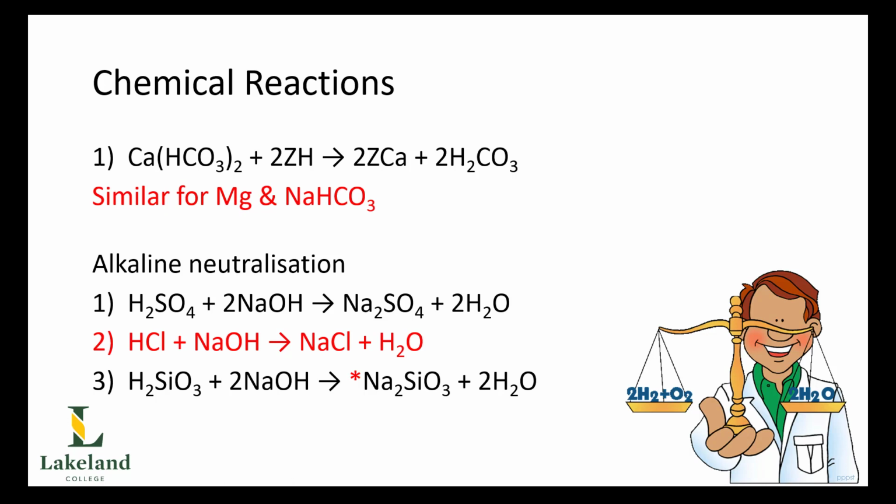Now, silicic acid, when it combines with our sodium hydroxide, causes a problem in that it forms sodium silicate. And the reason why we don't want sodium silicate is because this will produce an extremely hard and tenacious scale in the boiler. And it can also carry over and cause silica scaling downstream in end-of-steam users, like steam turbines, for example, when the pressure drops below 4150 kPa. So because we're producing sodium silicate on the effluent of this thing, that will have to be addressed in some other way. So how could we do that?